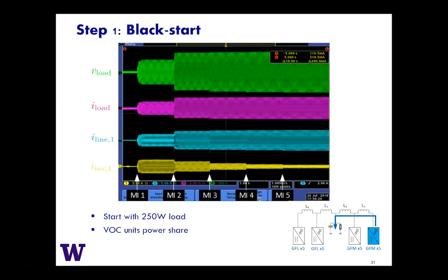A quick comment on that. There might be national lab people working on this specific problem. There was a utility that used an LM6000 as a black start, but it was leveraging the substation 280 MVA transformer, and that swamped out the inrush, swamped out the heatless combustion turbine. I'm pretty sure the question went to a national lab to help this particular California utility, so I might ask around.